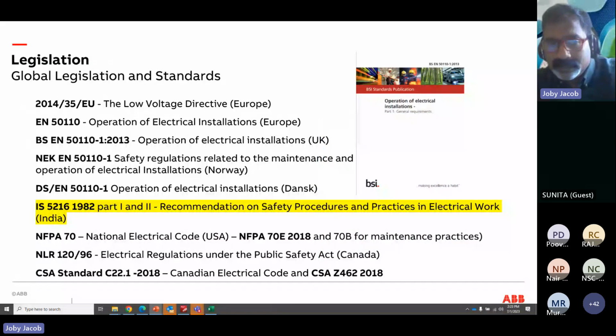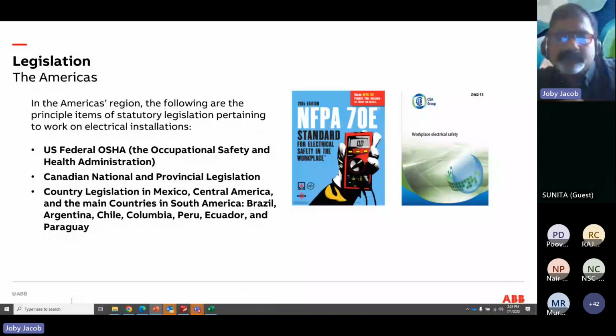There are various standards, particularly IS standards in India, 5216, a recommendation on safety procedures and practices in electrical work. I also know that we have an electrical handbook or something similar recently created by the national safety body. Then, when it comes to arc flash standards, American standards are predominant. NFPA 70 and OSHA, the Occupational Safety and Health Administration, require that every switchgear panel has to be arc flash studied. It's moving from America to Europe, and for some companies in India also, particularly starting with utilities, oil and gas. It's coming up.